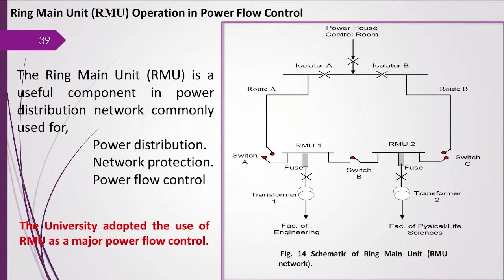When we closed switch B, we realized that the armored cable between engineering and physical science had also gone bad. We traced the fault on both Route A and Route B but couldn't find a means to supply power to physical sciences, bursary, and the environs. However, Madam VC graciously approved the replacement of the cable connecting RMU1 to RMU2, and that will be completed shortly.